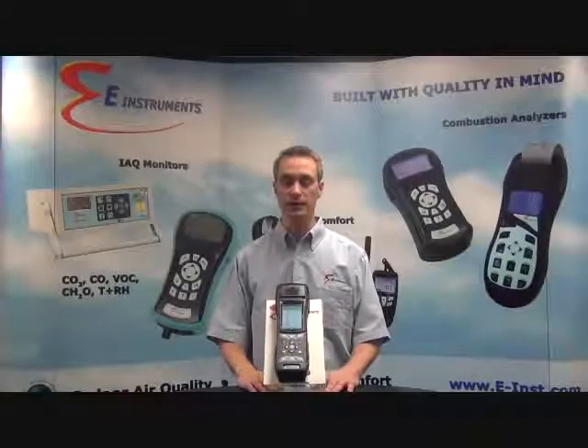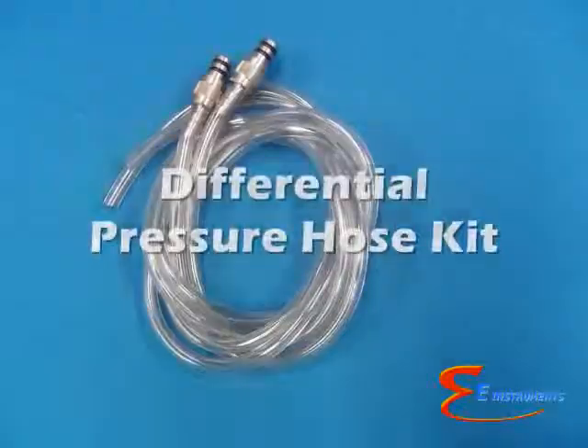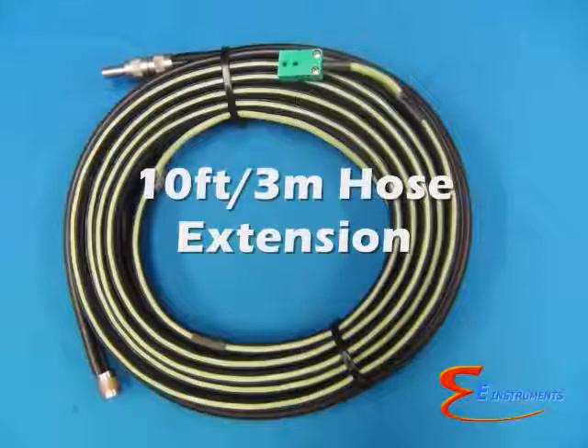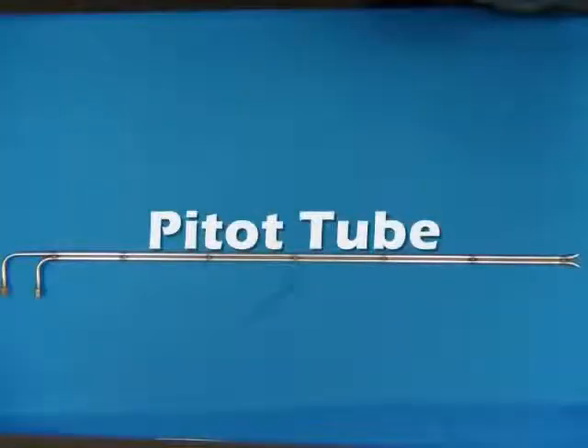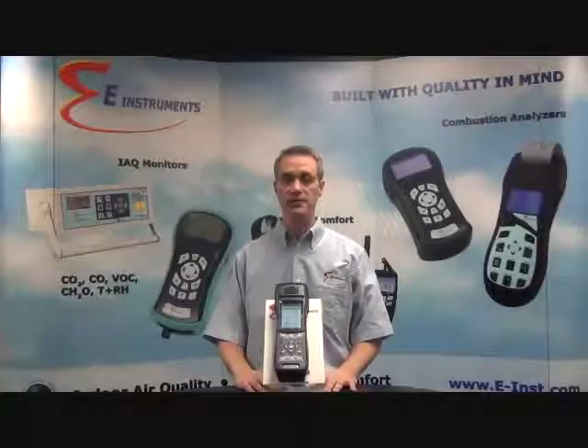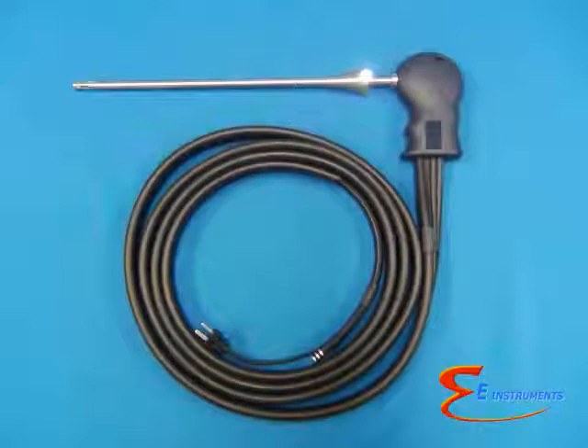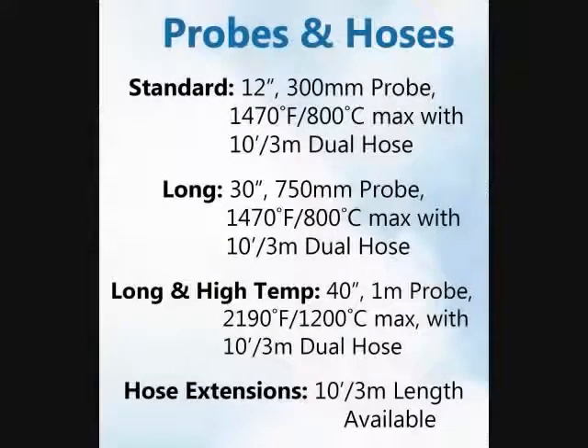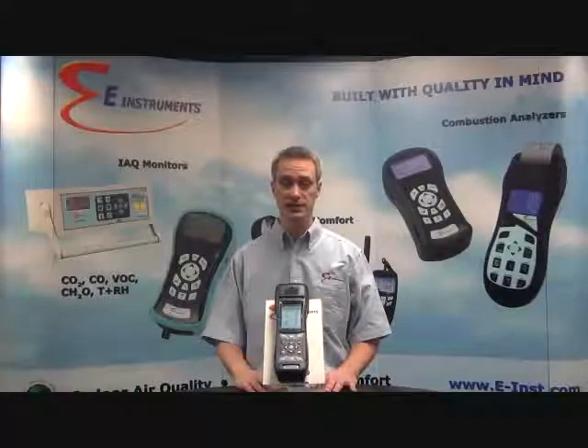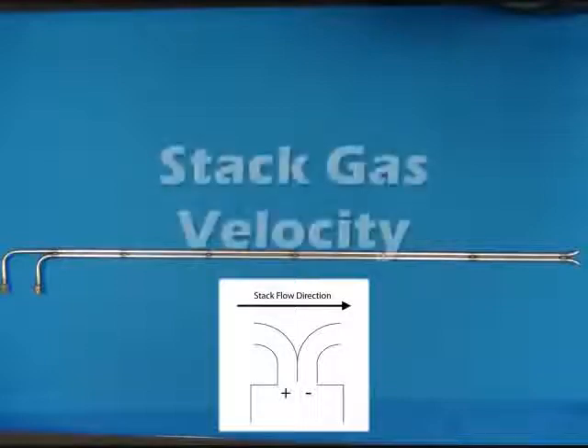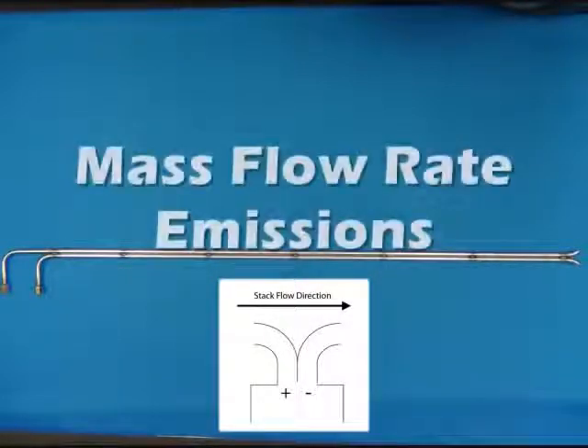Optional items that can be used with the E-4500 include a differential pressure hose kit, DC automobile charger, a 10-foot (3-meter) hose extension for use with tall or hard-to-reach stacks, and a pitot tube for stack gas velocity measurements. The standard gas sampling probe is a 12-inch (300 mm) long probe rated up to 1,470°F (800°C) and includes a 10-foot (3-meter) dual hose. Longer and higher-temperature probes and hose extensions are also available. An optional 36-inch (900 mm) S-type pitot tube can be used to measure stack gas velocity and allow for calculations of mass flow rate emissions.